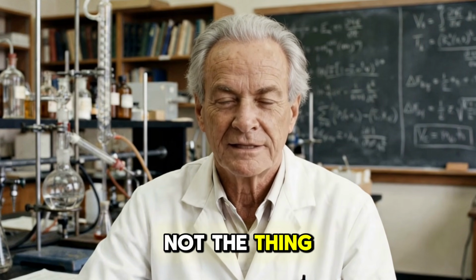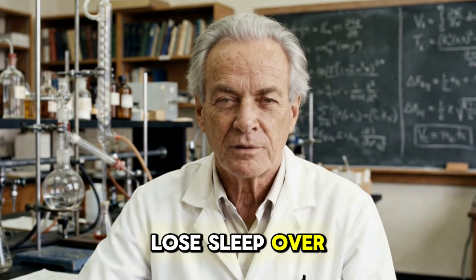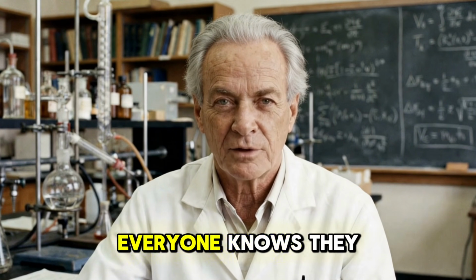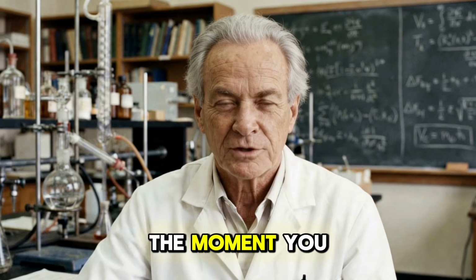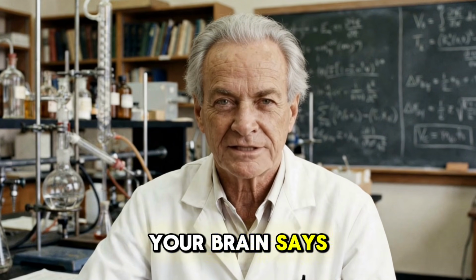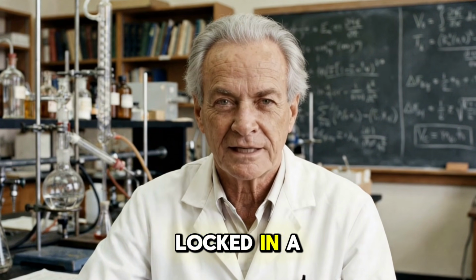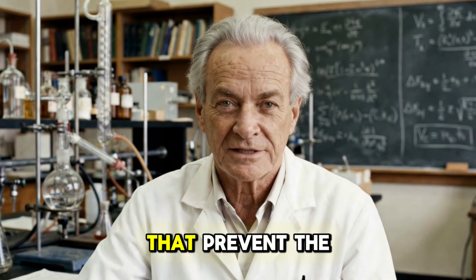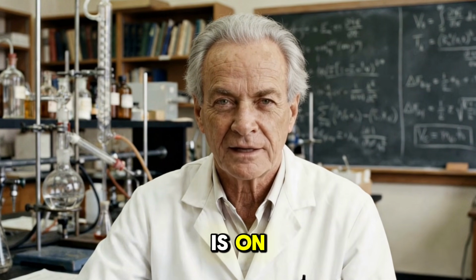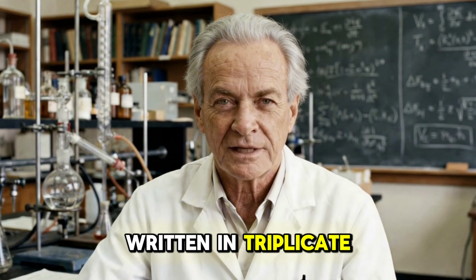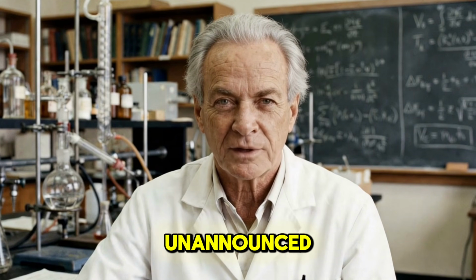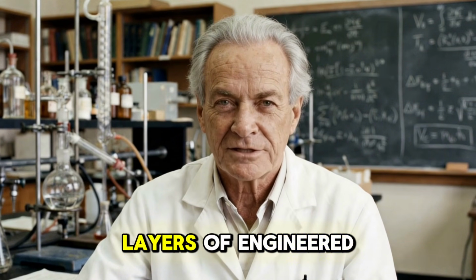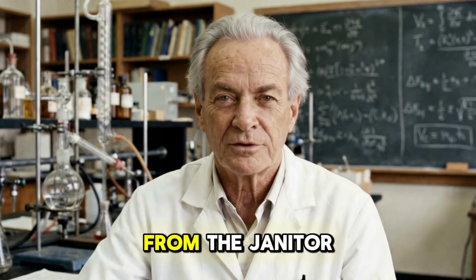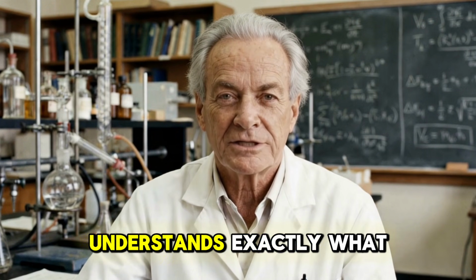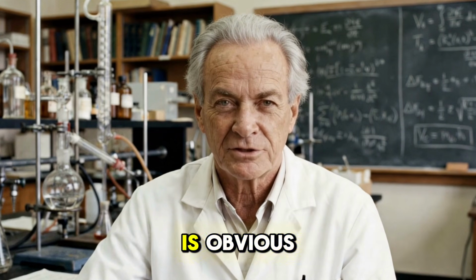But here is what most people do not realize: those sources are not the thing hospital safety officers lose sleep over. Why not? Because everyone knows they are dangerous. The moment you see that yellow sign, your brain says, do not go in there. The source is locked in a massive housing. There are interlocks that prevent the door from opening when the beam is on. There are protocols written in triplicate, inspectors who show up unannounced, multiple layers of engineered protection, because everyone from the janitor to the chief medical officer understands exactly what they are dealing with. The system works because the danger is obvious.